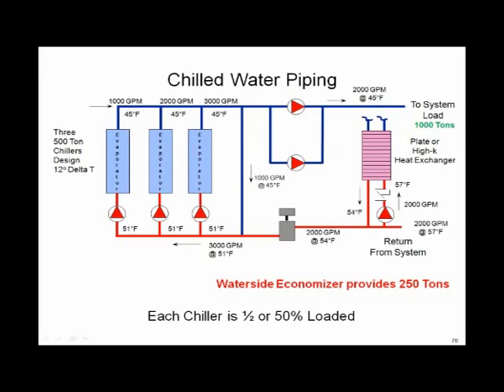In other words, you cannot stage these chillers based on flow. You cannot stage these chillers based on flow of the cooling load. So the cooling load, 2,000 GPM, didn't change. You're going to have to stage these chillers based on actual load. You may have to do some chill water supply reset temperatures in order to make it all work out. We can talk more about that later. Just want to caution you with that because it's an area that people who try this for the first time have a little bit of trouble with, and I'm trying to make sure that they grasp it.